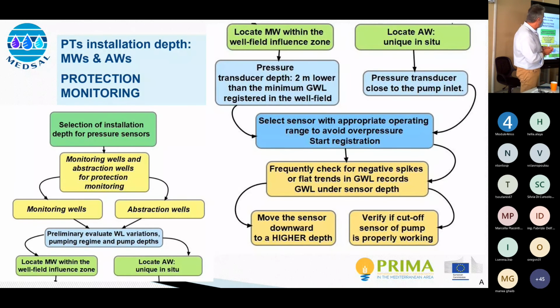Typical rule of thumb: the pressure transducer depth should be at least 2 meters lower than the minimum groundwater level registered in the well field, and the pressure transducer should be close to the pump inlet. In any case, this way you're going to make sure that you're not going to be missing any measurements. Theoretically speaking, the depth of the pressure transducer should be even below the pump inlet, so that you're not going to lose absolutely anything in terms of measurements.